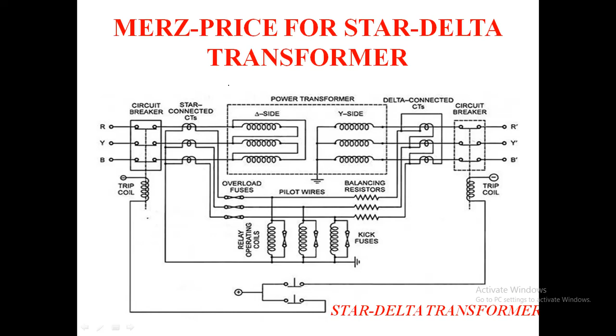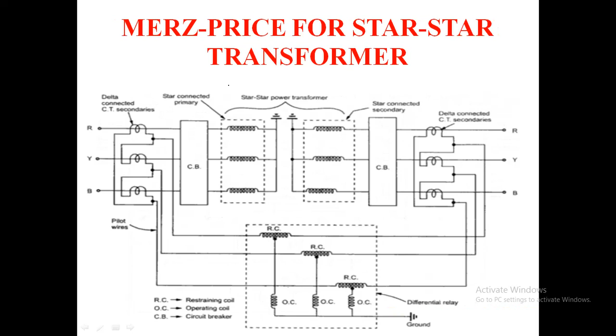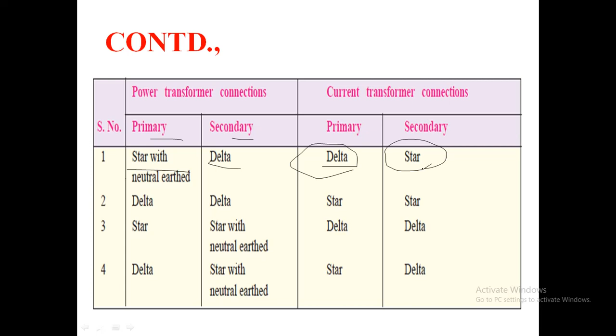So we have explained the protection for the star delta transformer. So this is your star to star transformer, and this is our tabulation for power transformer connection and current transformer connection. For the power transformer, the primary is star with the neutral earthed, and the secondary side will be delta. For the current transformer, the primary will be delta and the secondary will be star connection.